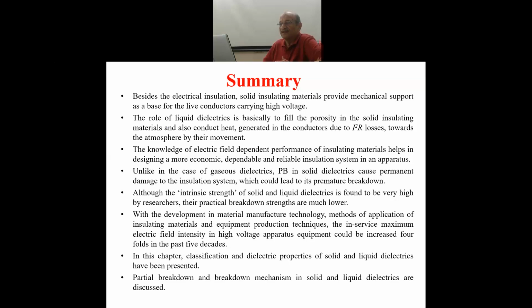Besides the electrical insulation, solid insulating materials provide mechanical support as a base for the live conductors carrying high voltage. Not just electrical insulation, the solid also provides mechanical support to the live conductors. Just like you can say in the case of the insulator string in transmission lines, that is providing both electrical insulation as well as mechanical support.